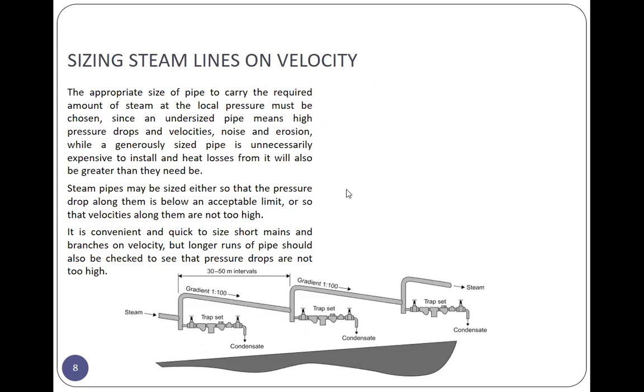Next, sizing steam line on velocity. Based on velocity, the appropriate size of pipe to carry the required amount of steam at local pressure must be chosen. Since an undersized pipe means high pressure drop and velocities, noise and erosion, while a generously sized pipe is unnecessarily expensive to install and heat losses from it will also be greater than they need be. Steam pipe may be sized either so that the pressure drop along them is below an acceptable limit, or so that the velocities along them are not too high.